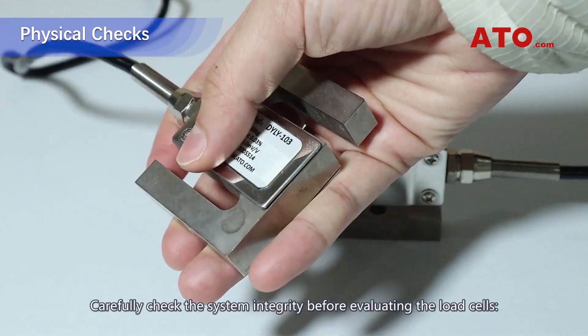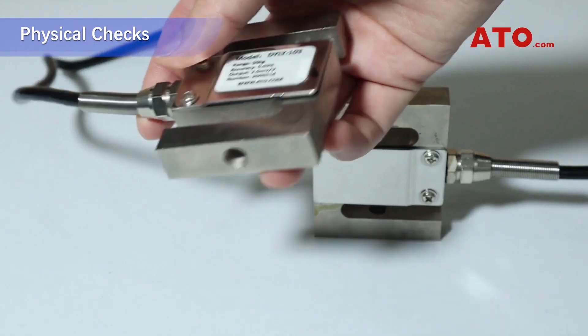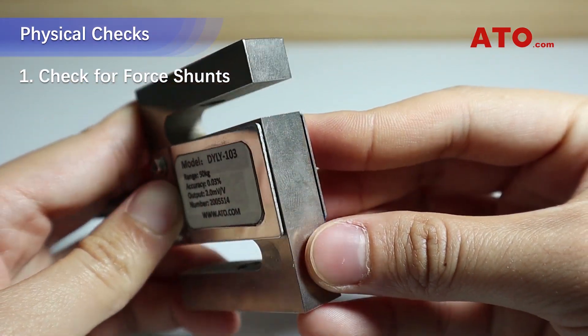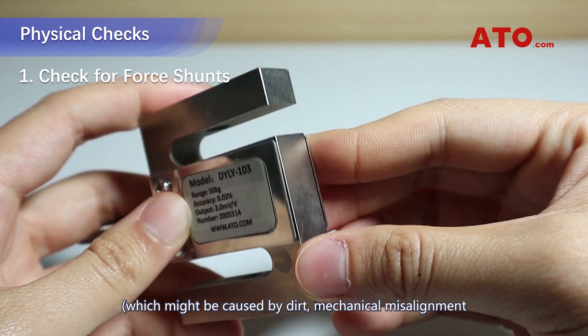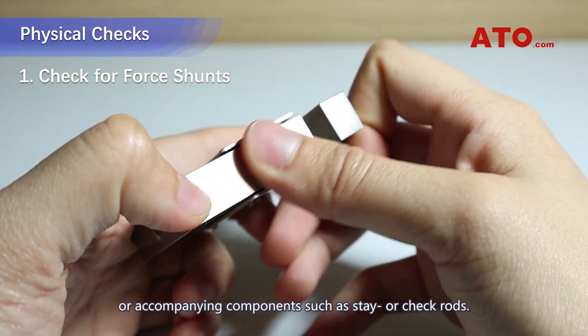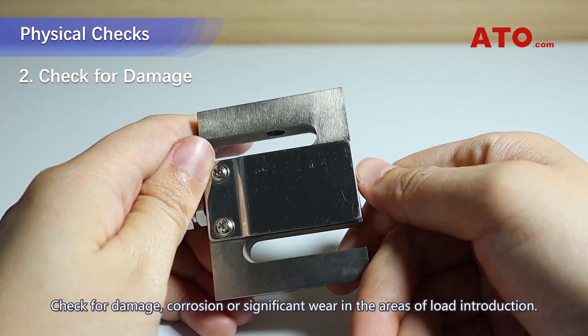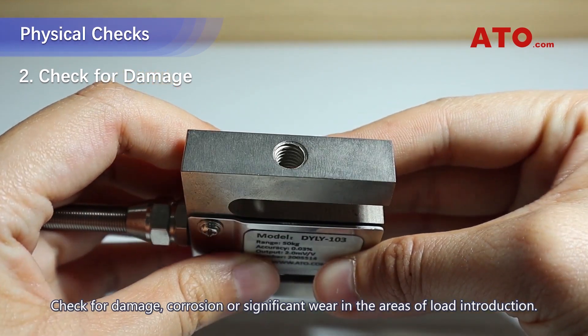In general, carefully check the system integrity before evaluating the load cells. Check for force shunts, which might be caused by dirt, mechanical misalignment, or accompanying components such as stay or check rods. Check for damage, corrosion, or significant wear in the areas of load introduction.